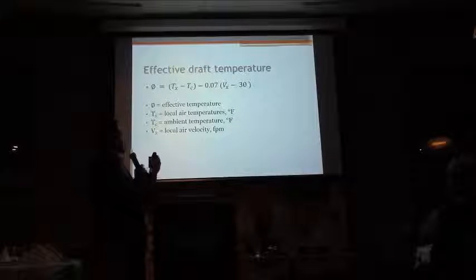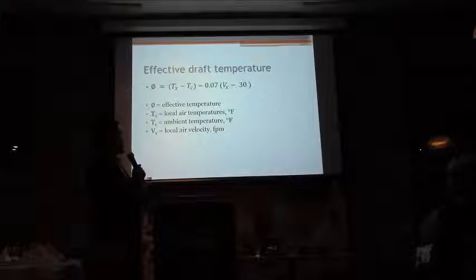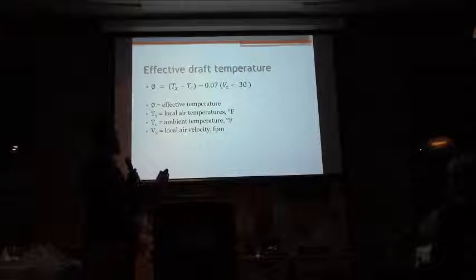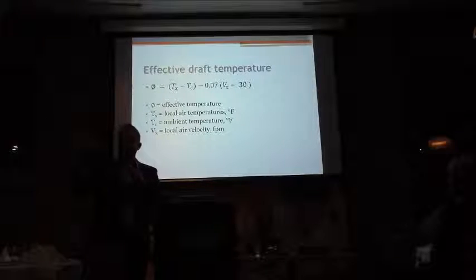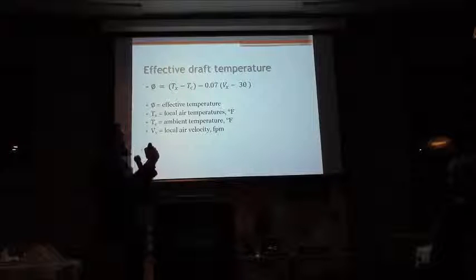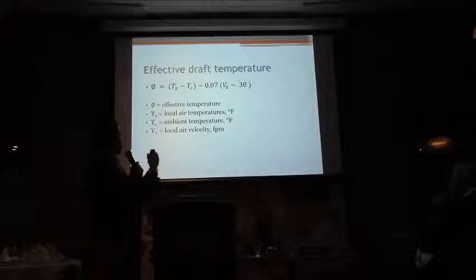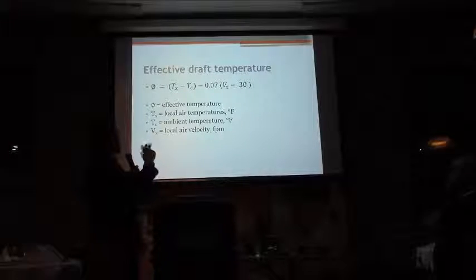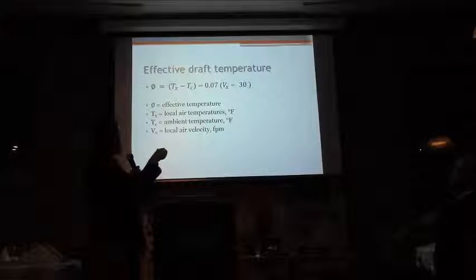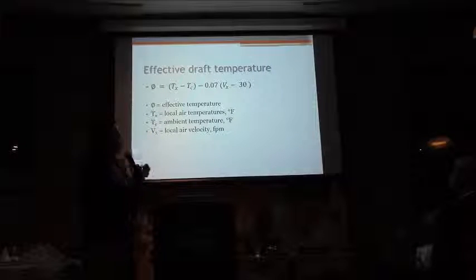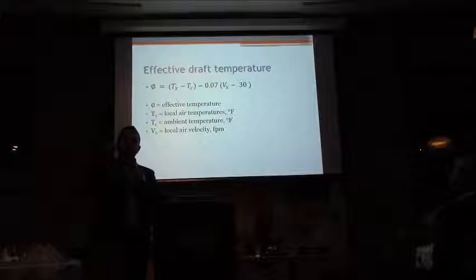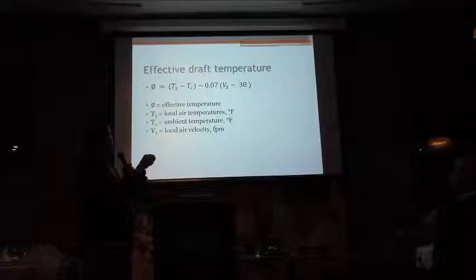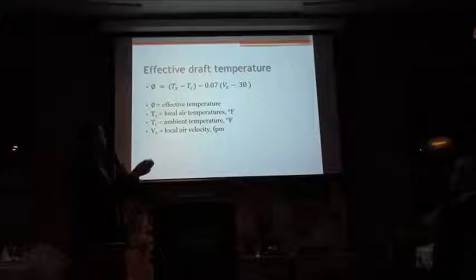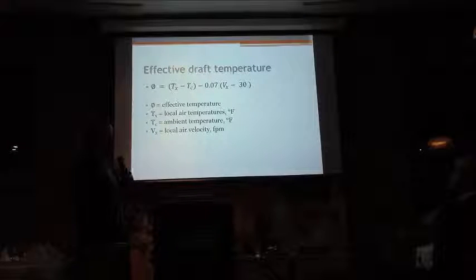And ASHRAE, they invented something called the effective draft temperature to help us keep track of all these factors in one single formula. So the effective draft temperature depends on 3 variables. You have Tx and Vx. So those are local temperature and velocity measurements anywhere across the room. And Tc is your set point temperature or your ambient temperature.